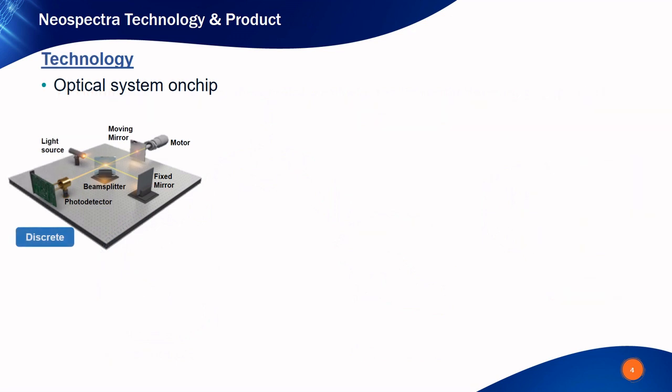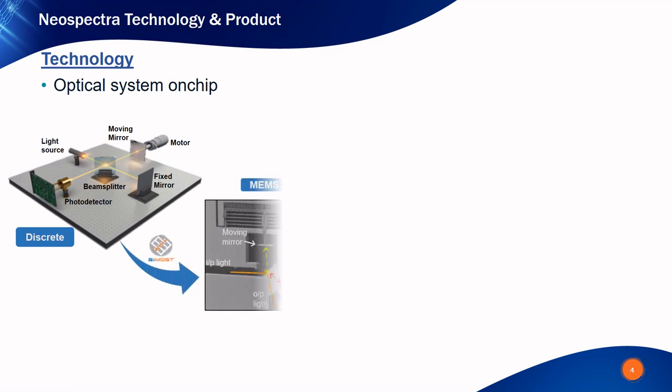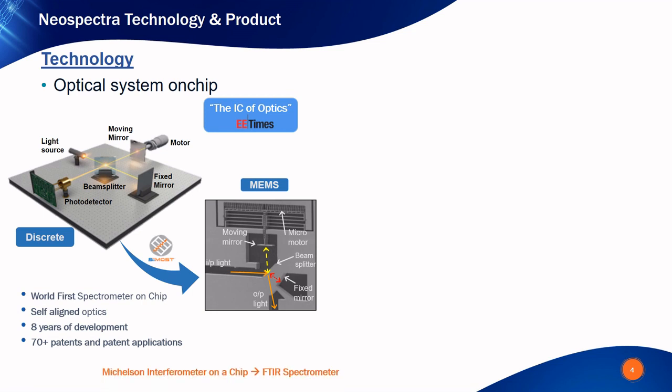Conventionally, optical bench systems are bulky and expensive. Shown here is an example of a Michelson interferometer, which is the core engine of the FTIR spectrometer. Normally, building such a device in a discrete way and aligning the optical components can consume a whole day. In Si-Ware Systems, we have developed the micro-optical bench technology, sometimes referred to as the integrated circuits of optics. It is based on micro-electro-mechanical systems (MEMS) technology. All components of the interferometer are self-aligned and monolithically integrated on a silicon chip, making this solution much more reliable than bulky devices and enabling huge cost reduction following the rules of economies of scale.